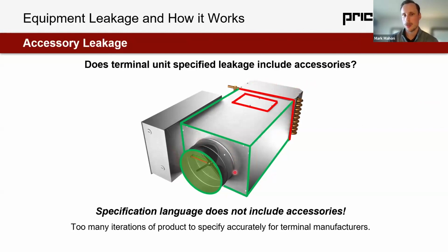Now, we seal our own wall penetration. So we put silicone caulk on that in the factory. I see some contractors still reseal that in the field just to reduce risk. I would say that's not necessary. I would also say it's unnecessary to seal the seams of the terminal, but some manufacturers have worse leakage performance. So it's maybe something to even consider. I think it's over the top and not required though. As far as the access door goes, I'm just going to change back to my mouse.